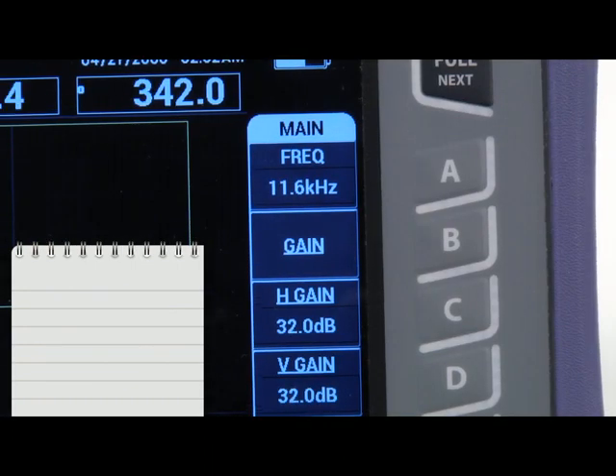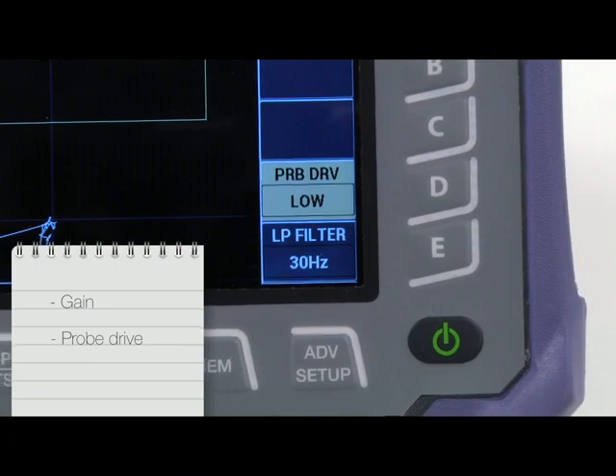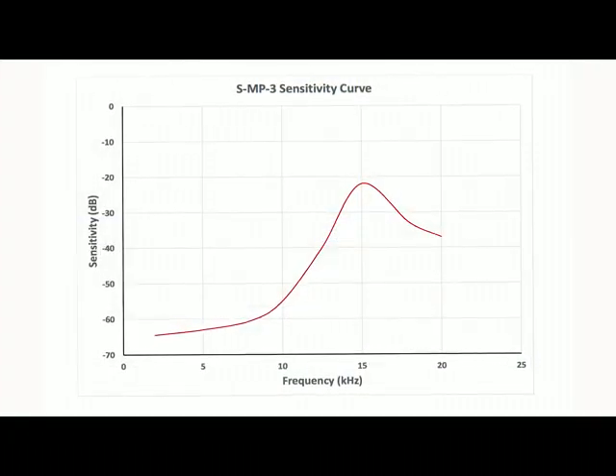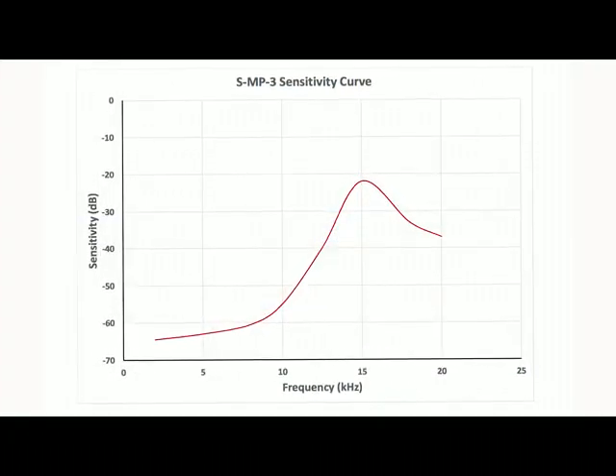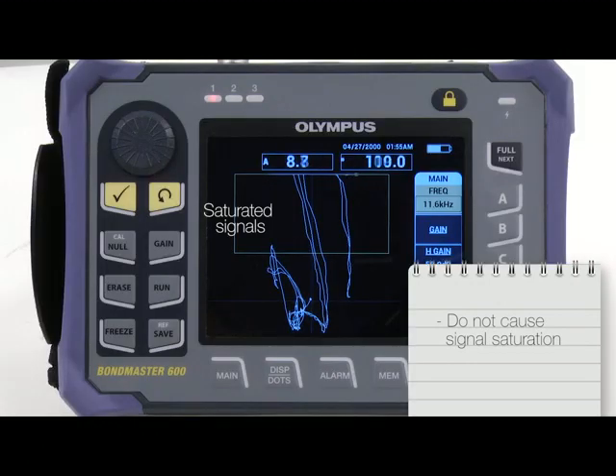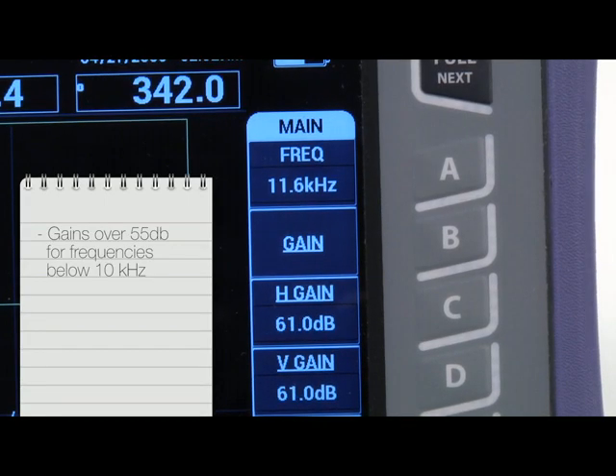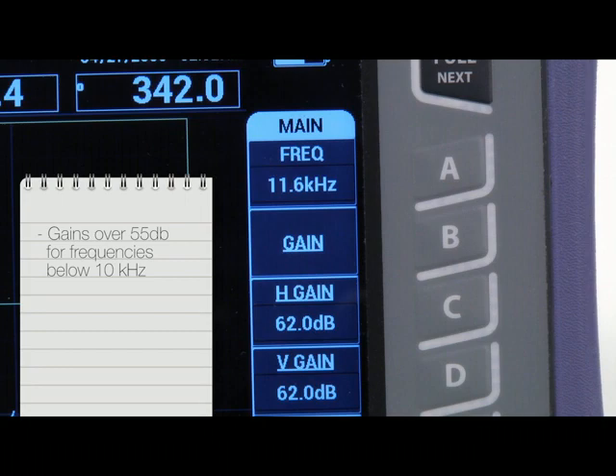The next critical parameter to set is the gain and/or probe drive. Since the MIA probe exhibits a strong difference in sensitivity along its frequency range, it is critical to ensure that the combination of gain and probe drive does not cause signal saturation.